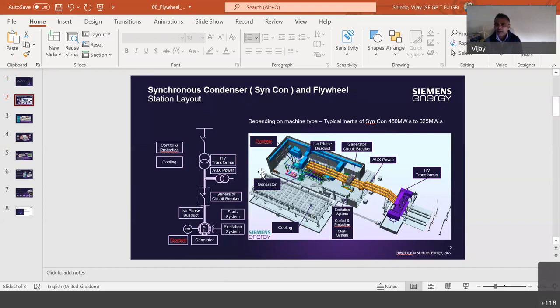When we say synchronous condenser, it is nothing but a synchronous machine without any kind of turbine. This synchronous machine, however, is designed and optimized to offer the solution for short circuit level and/or reactive power. So that's how it differs from the normal synchronous machine. And this synchronous machine is rotating at 3000 RPM if it is a 4-pole machine or a 2-pole machine, depending on that. Since it's operating at a synchronous speed, it offers a very good amount of synchronous inertia to the system.